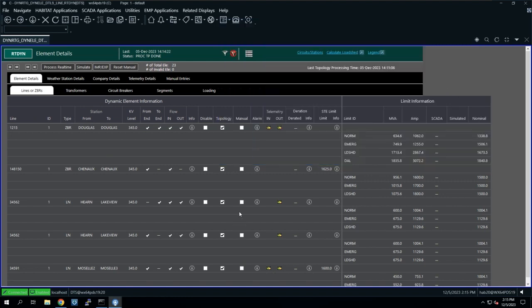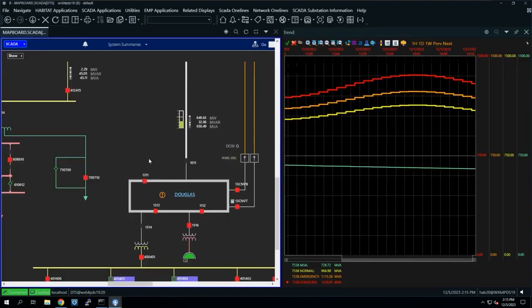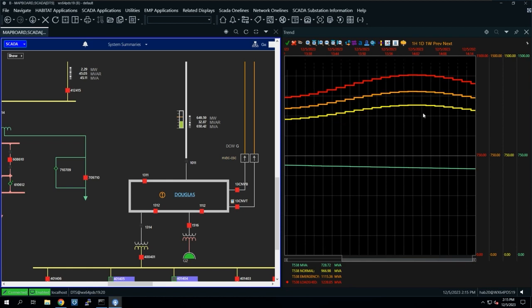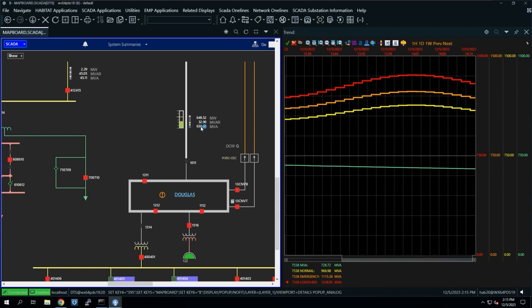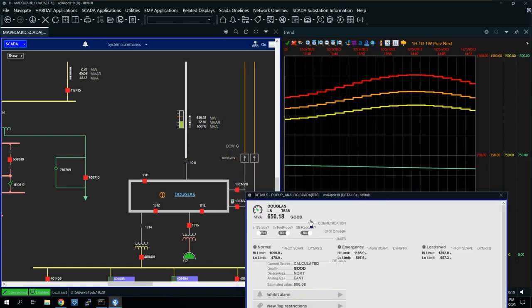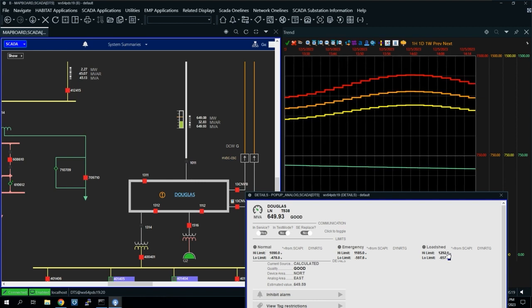To see how the application works in real time, I've got a display pulled up here. So we've got our Douglas to Hanover transmission line. Basically, we've got a demonstration here where we're using field-based digital dynamic line ratings. You can see that our ratings are changing over time due to the changing ambient conditions. The RTDyne application is using the SCADA API to write, like I had mentioned before, the ratings from RTDyne to SCADA and also to our network application. So you can see here that it's writing in these limit values for the normal, emergency, and load shed. And as those field conditions change, we're going to be updating those ratings consistently.